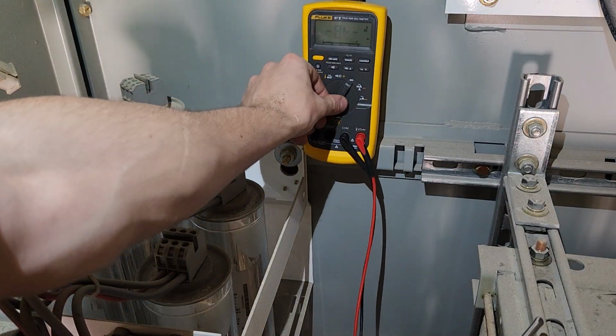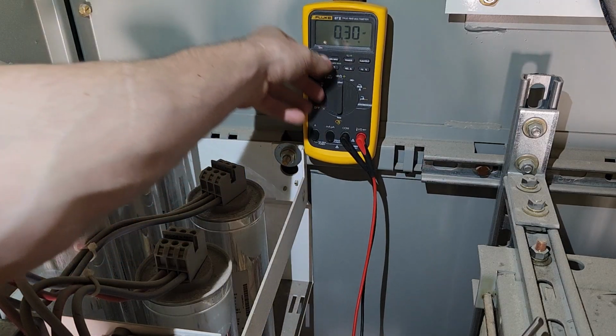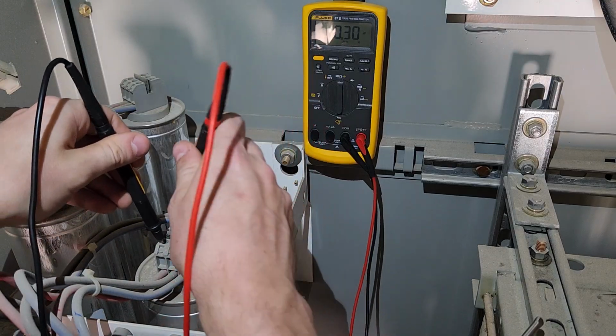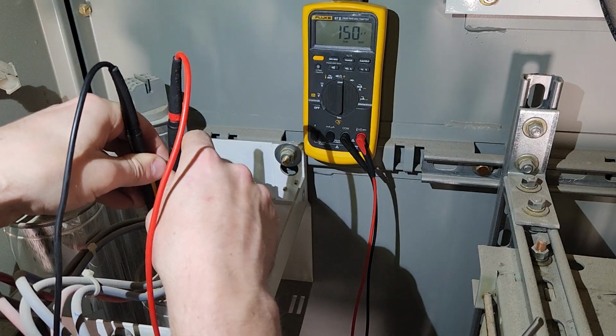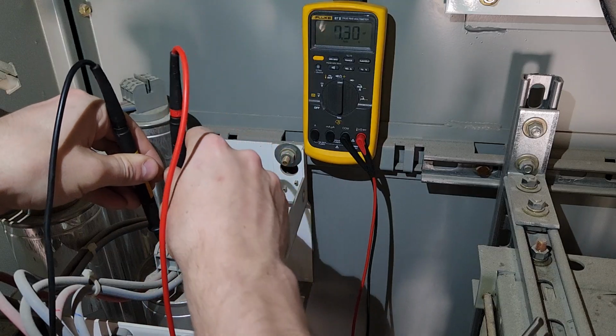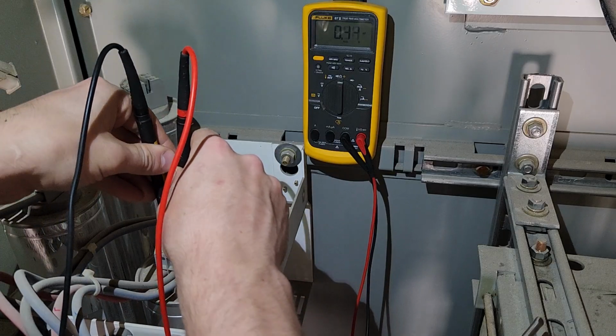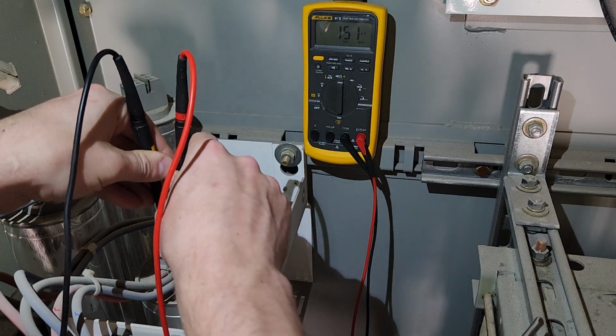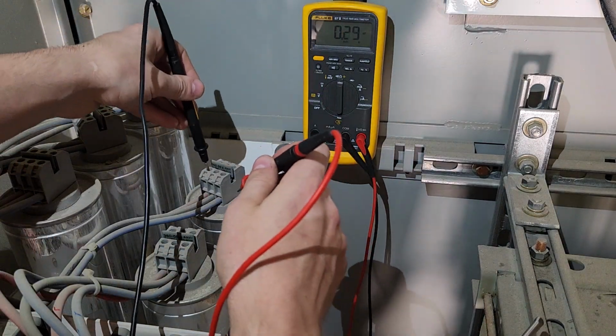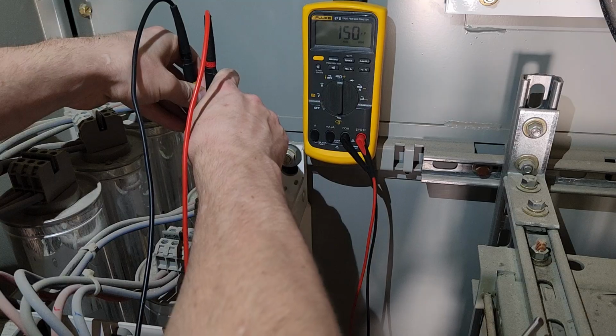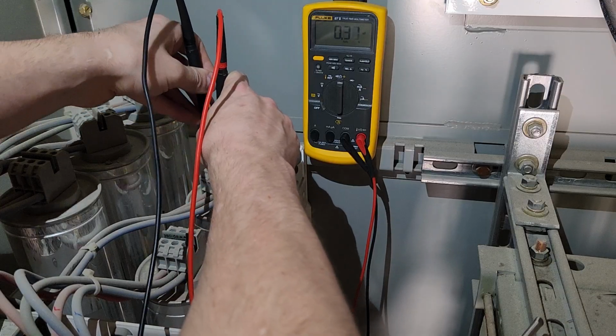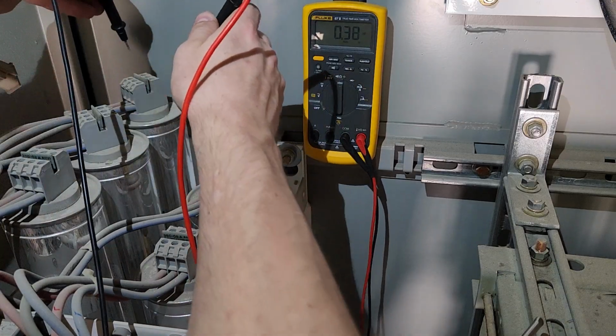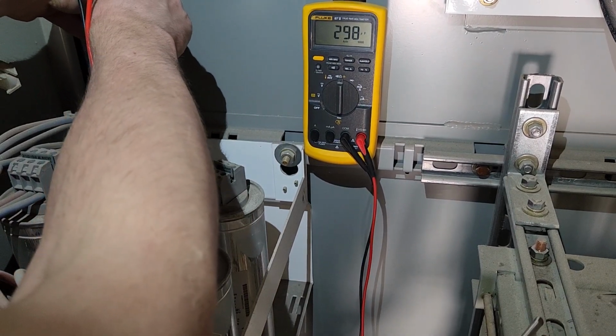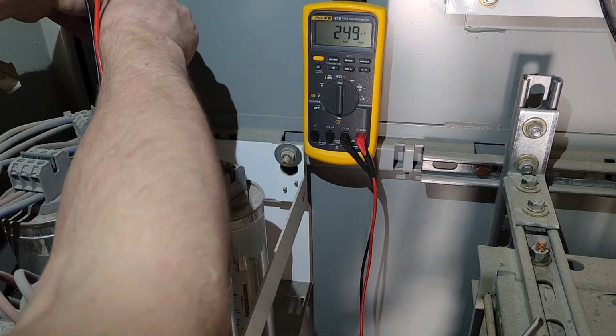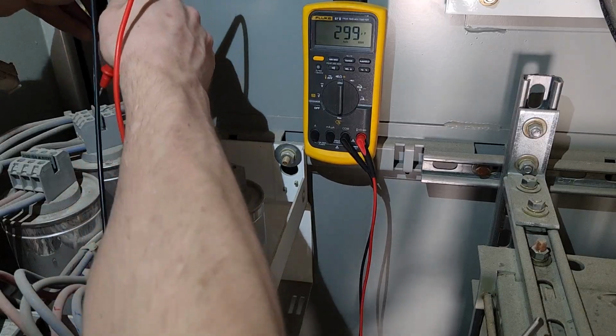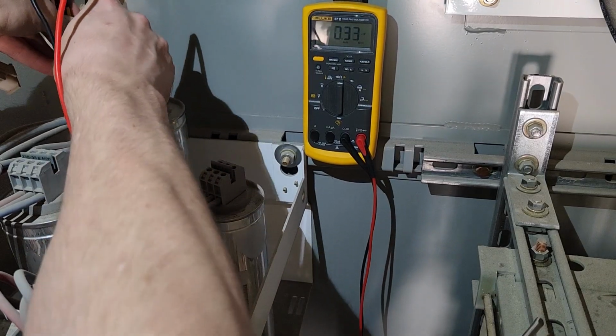I'll go to diode capacitance, nanofarads, so we should be getting about 100. What does that say? Yeah, 150. This is stabilizing very quickly as well, which is good. 150. I'll have to double check with the manual specs, but I'm pretty sure it was 100 for this 17.5 kVAR rated bank. I think 200, and maybe it's just 200 amps fully loaded. So that's 300 nanofarads. Where's that micro? I don't remember. 300. That's good. This seems about right.